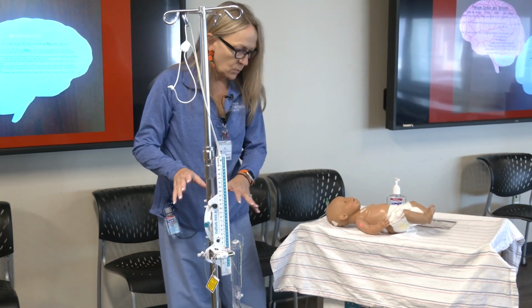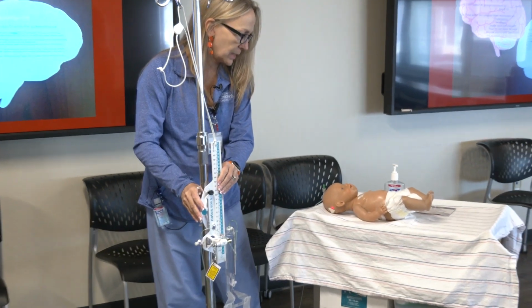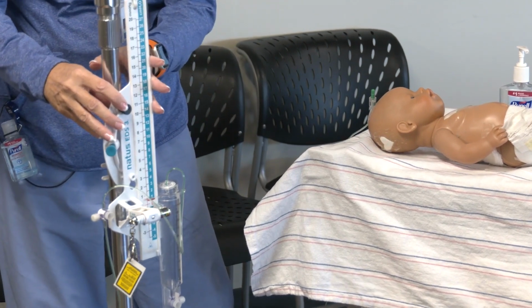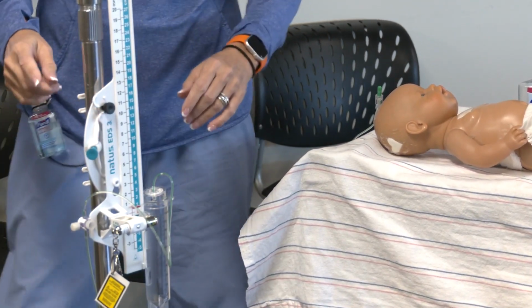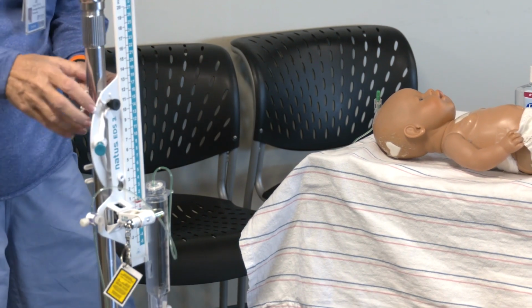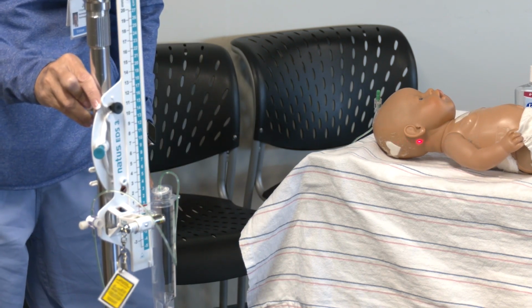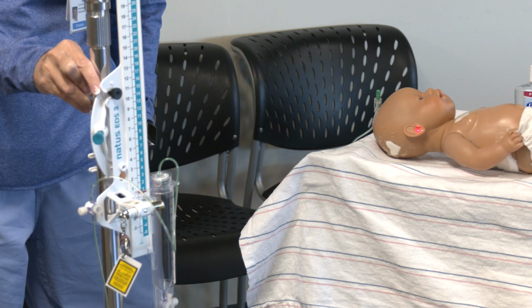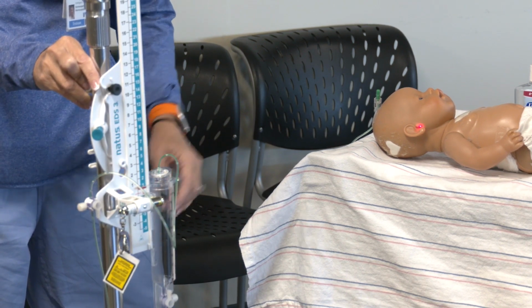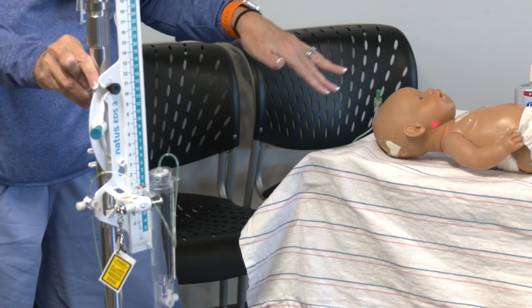So it's on right now. We can't always move things around, but we can slide this around to kind of get in the right plane. And as you see, it's not on the tragus. It's too low. So you're going to use the same green screw that you put it on the pole with to loosen that, to raise it up. Light went off. There, you can see where the laser is now. So I'm going to raise it up on the pole until I have the laser light on the tragus, because this end is at 0 and now it's at the tragus 0. So that's what it means by zeroing to the tragus.